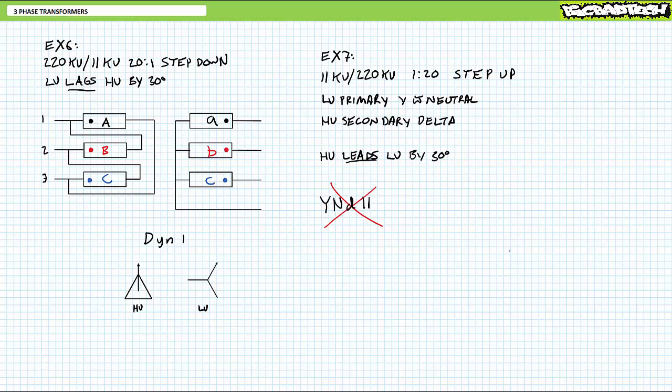Pay attention to the dramatic emphasis I'm placing on certain terms. I say again, consider a step-up transformer with a Y-configured low-voltage primary input and a delta-configured high-voltage secondary output where the high-voltage output leads the low-voltage input by 30 degrees. Let me remind you that the standard nomenclature format indicates the high-voltage side first in capital letters, the low-voltage side second in lowercase letters, and the phase shift of the low-voltage with respect to the high-voltage side using clock notation.